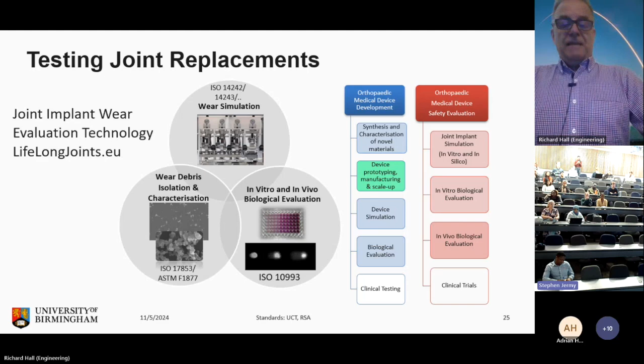The top one is running a standard ISO cycle. Now, standard cycle comes from data that was largely released in the 1960s by a guy called John Paul, who worked at Strathclyde University. And you can see in the diagram to the left of the top simulator, that is the axial load that's being applied to the particular joint. So you get two peaks, which are synonymous with heel strike and toe off. You get a flat period or a low load period during the swing phase. Could someone suggest what the problem is with that?